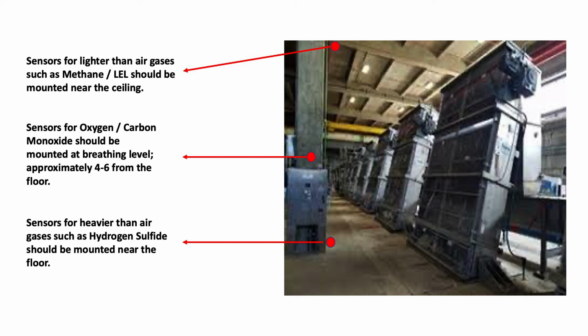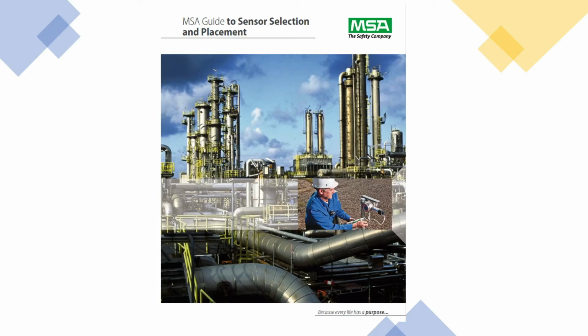Methane gas is lighter than air, so the sensors should be mounted up high in a room near the ceiling. Oxygen and carbon monoxide should be mounted 4 to 6 feet from the floor, or at breathing level, while hydrogen sulfide is heavier than air and should be mounted near the floor. MSA has this handy guide to use for reference. Feel free to contact us or email me for a copy of this guide. Our contact information will be provided at the end of this presentation.